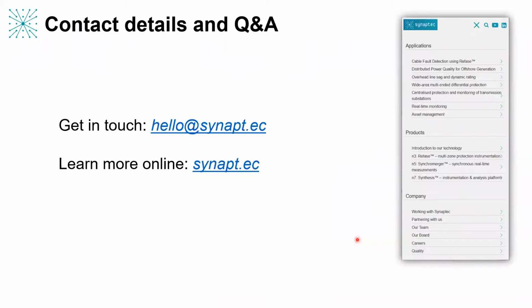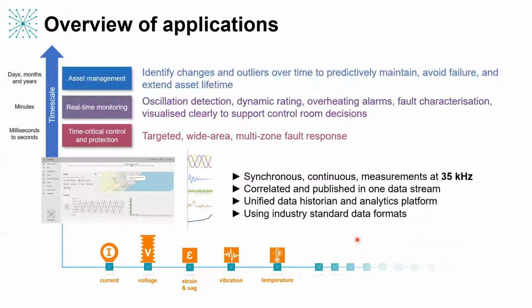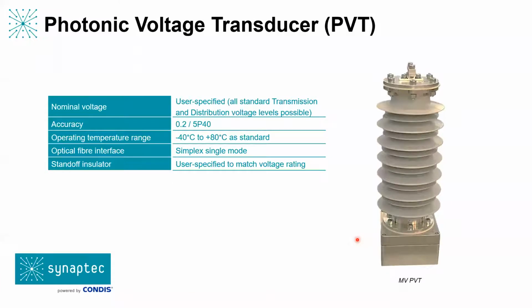Let's go back to the technical sheets on the sensors, just so that I can describe the inputs and outputs from them and connections. So let's take this as an example. Here we have a medium voltage sensor measuring up to 70 kV. The top of that is going to be live, and the lower part is going to be earth. And we're going to be measuring the potential between those two. The sensor is embedded inside it. The fiber is the only connection to the external systems. We have a fiber in and one fiber out, dielectric, single mode, no copper in and out whatsoever.